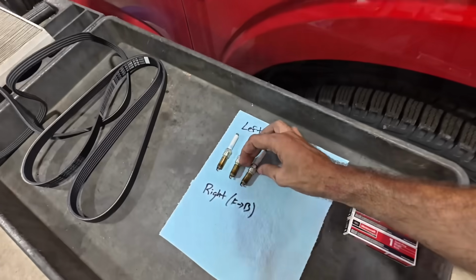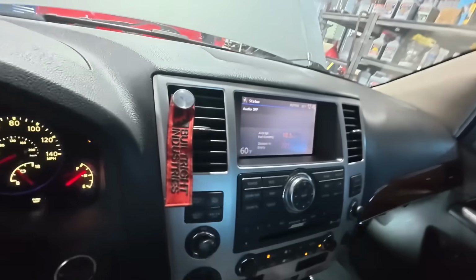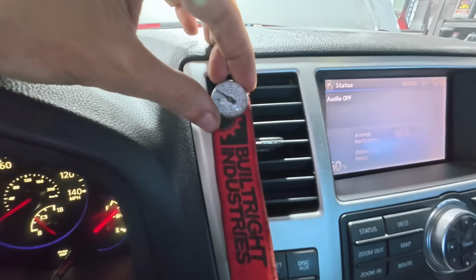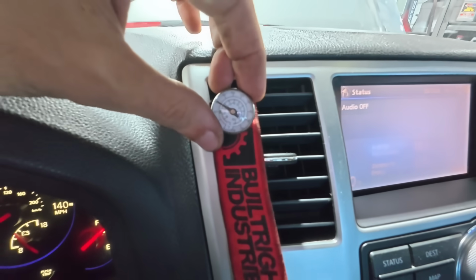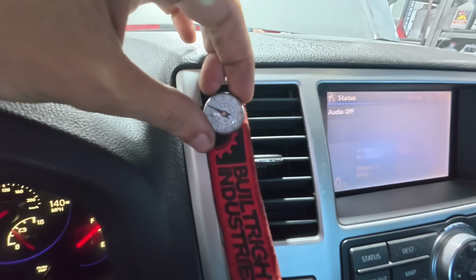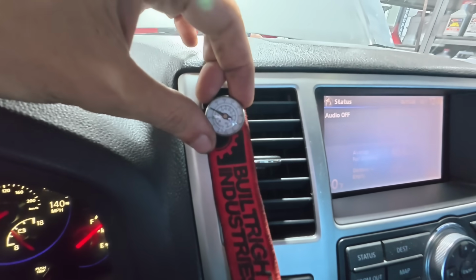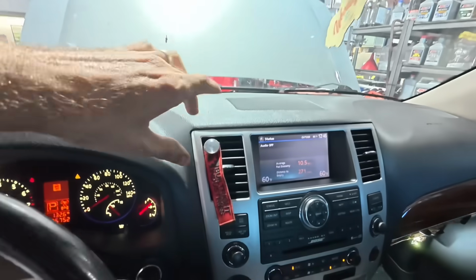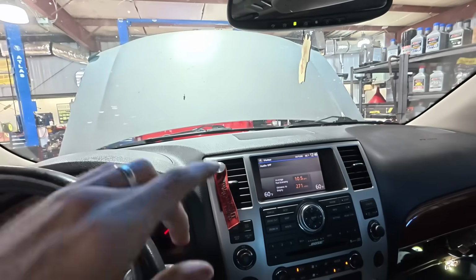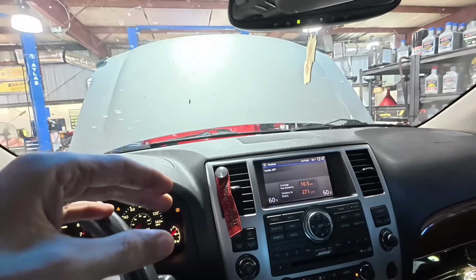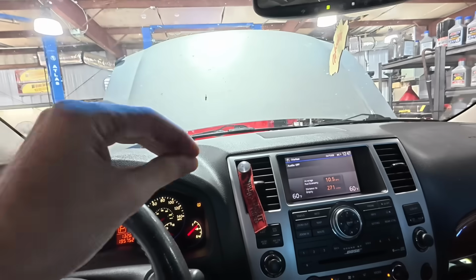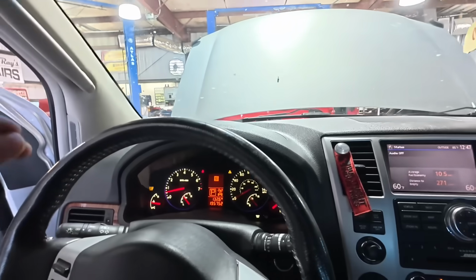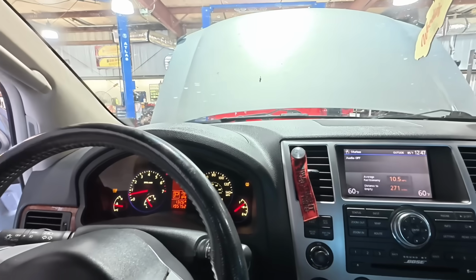All right, let's do one more recheck real quick and see where we're at. We're hanging out just under 60 degrees while stationary, 94 degrees outside. That means we got a 34 degree temperature drop based on static conditions, and considering the high heat and high humidity today, the system is functioning flawlessly by my estimation at this time.